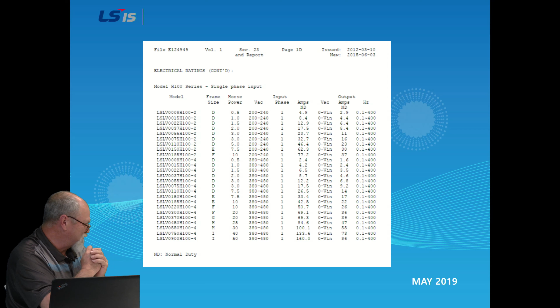That's correct. This is our H100. Again, I'm very proud of this product. We've just launched it up to 800. It's a dedicated VFD for the pump and fan industry. It's 120% overload for 60 seconds. Of course, we talked about it briefly with the built-in communications aspect. It is volts per hertz because you don't necessarily need sensorless vector to turn a pump. But I can do output frequency up to 400 hertz.